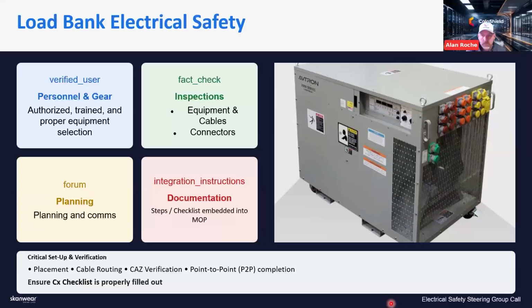Placement, cable routing, and controlling the areas matter too. We see a lot of load bank cables laying on the ground without a barricade, where workers can cross over, step on, or trip on them. We never want that - you want to barricade those areas off, and point-to-point checks should be completed when doing these lineups.